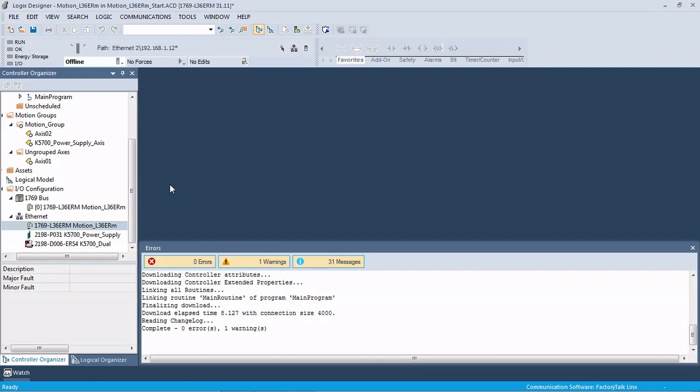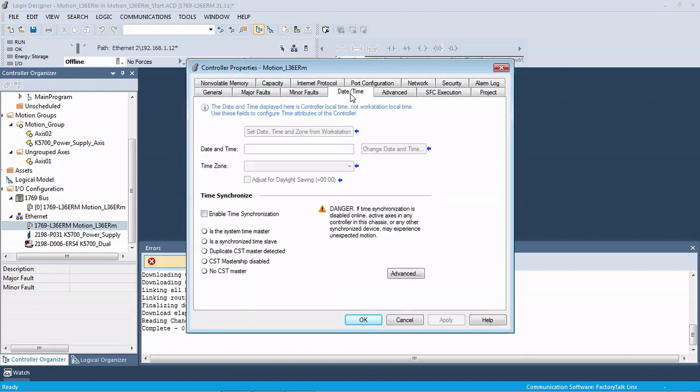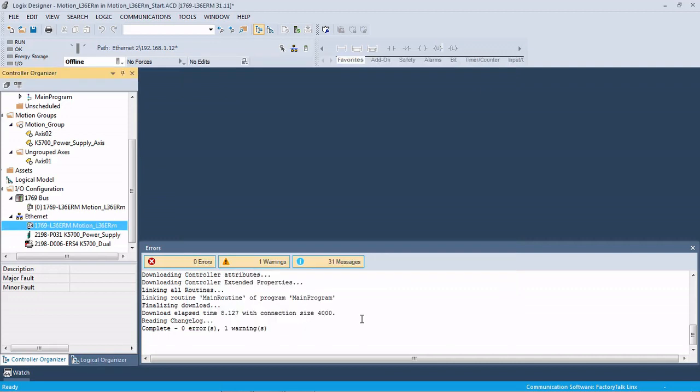One thing that we forgot to mention before downloading - there's a couple things we need to change. The first thing is in your controller properties. You need to go to date and time and enable time synchronization. You'll need to do this for any motion application that you're doing with integrated motion. This will allow the controller to be the time master. Without that, you would end up getting a fault on the drives when you go online saying there's no time master enabled.